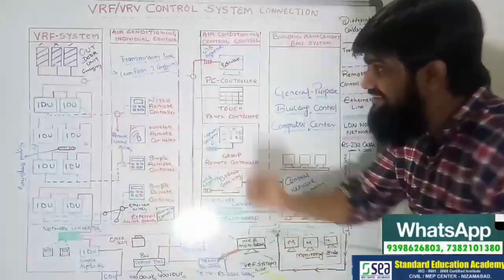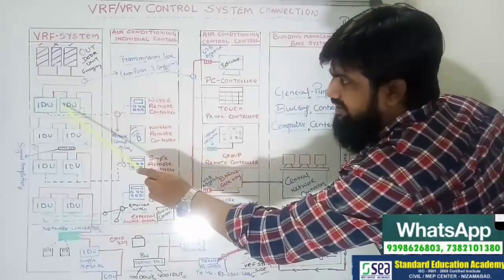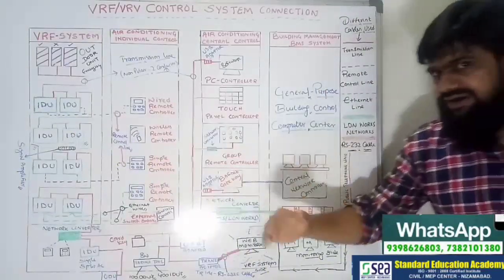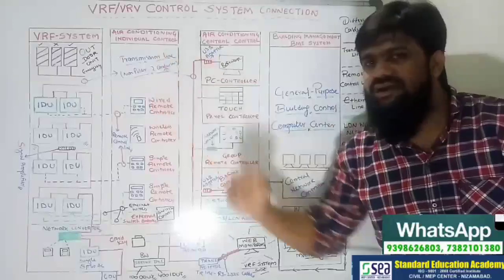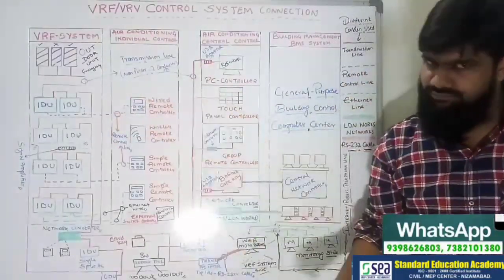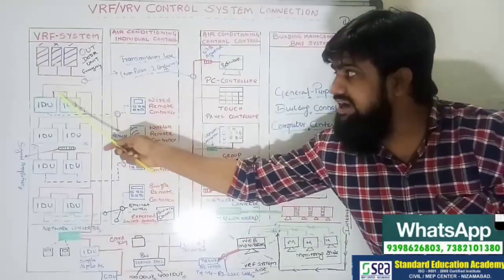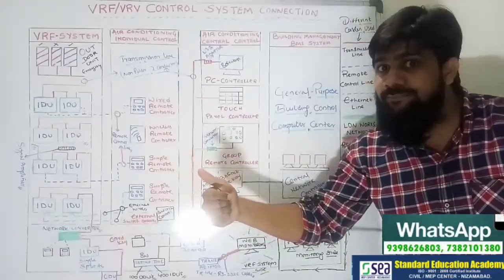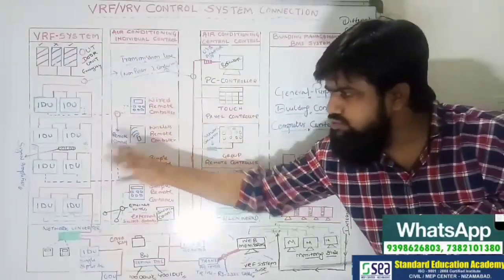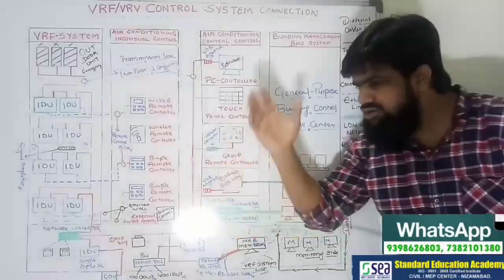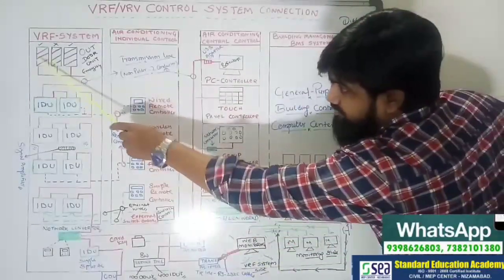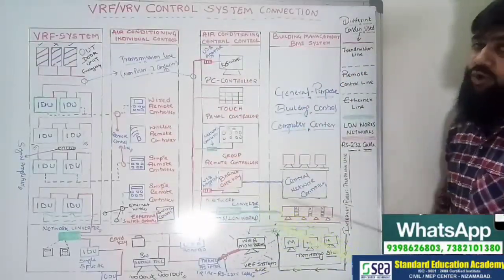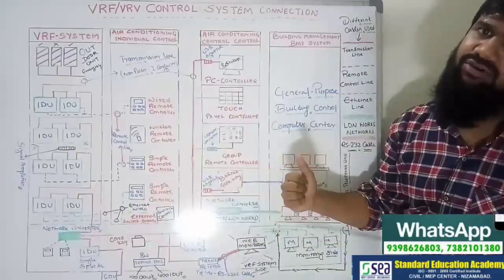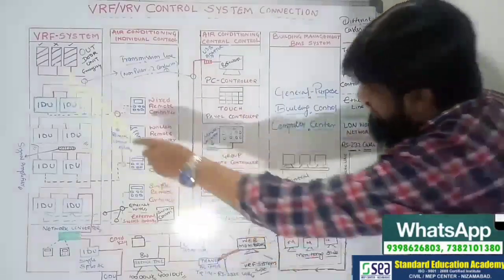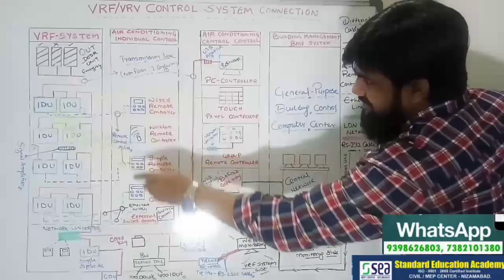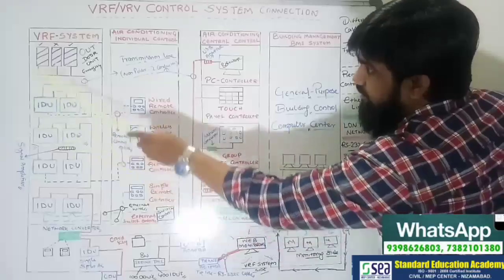This DC inverter compressor is directly controlled or signaled by the electronic expansion valves of the individual IDUs. From each IDU, the electronic expansion valve sends its signal to the outdoor DC inverter compressor. As per the signal sent by these red transmission line wires, the outdoor unit will send back the refrigerant that was required by the IDUs, not a constant amount, because this compressor works on variable speed. This variable speed is achieved with the help of the inverter compressor; a DC inverter circuit is there, and sine wave inverters are applied within the compressor.